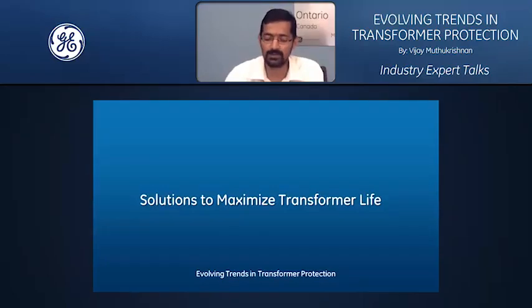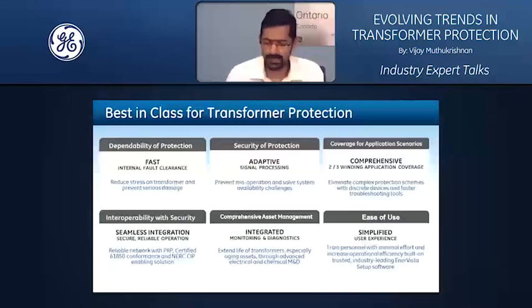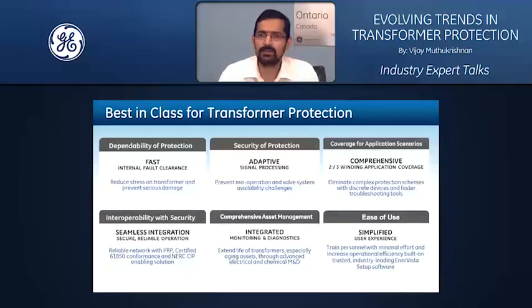Now, when you think about it further, what can be best in class in transformer protection? What are the various dimensions of a best in class transformer protection relay? The fundamental aspect of any protection relay is reliability. In protection philosophy, reliability can be looked at in two dimensions. One, dependability of protection. Dependability means the ability of the protection relay to clearly remove the fault, when there is an in-zone fault, in the fastest manner possible. The real impact of that speed can be felt by reduction of stress on the transformer as well as preventing serious damage. This is one dimension of reliability.